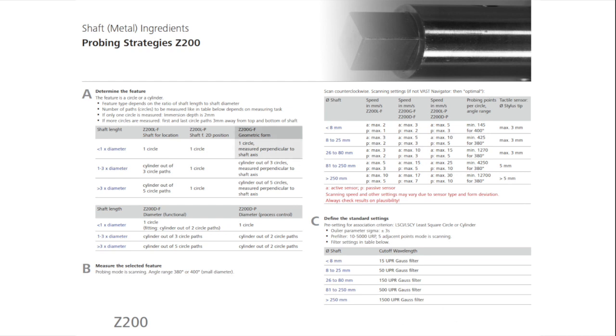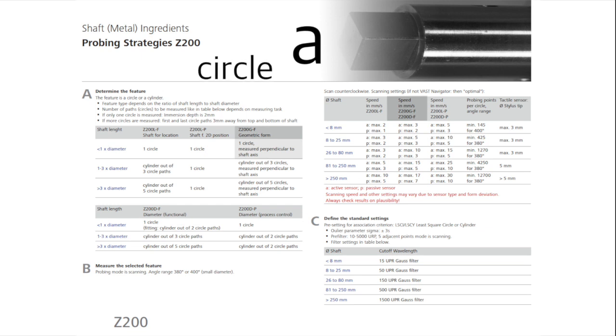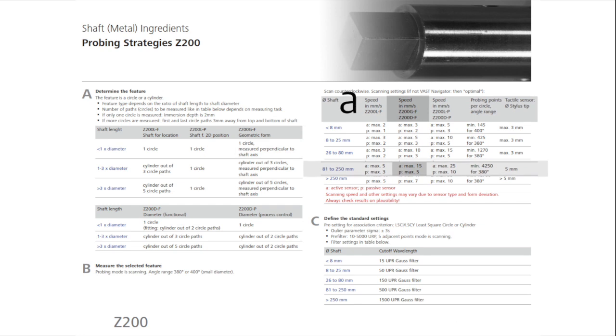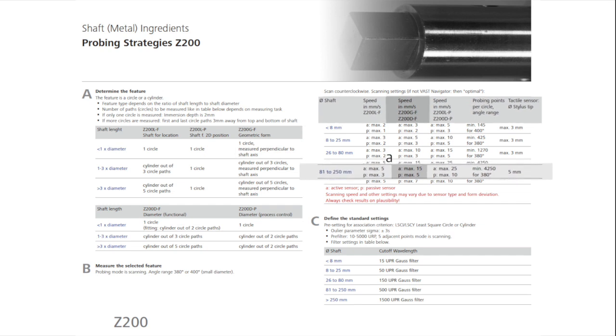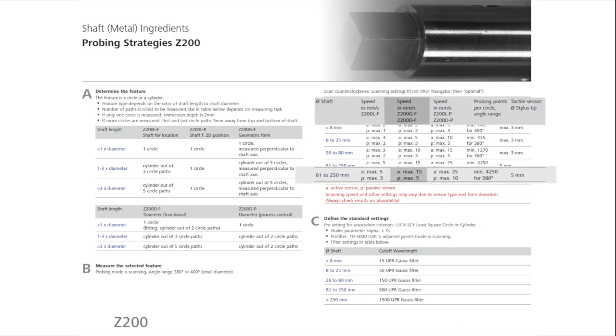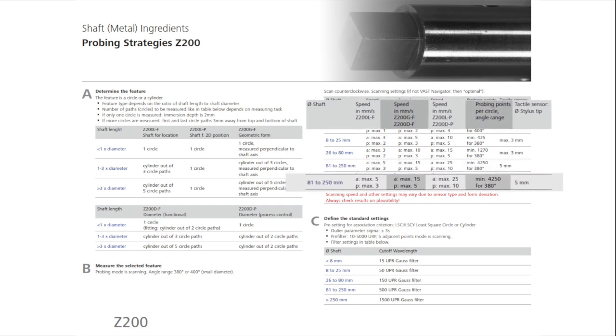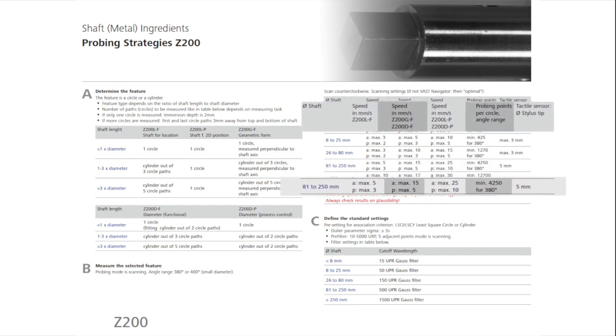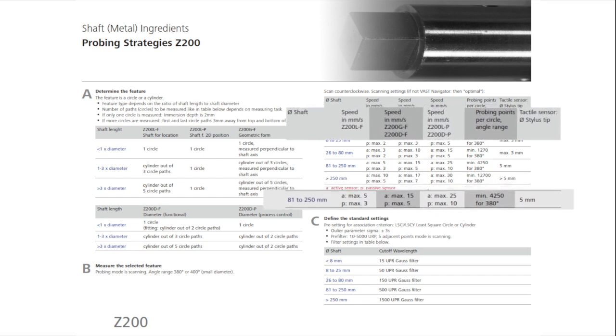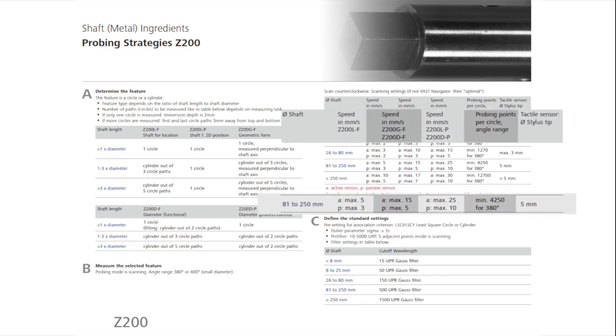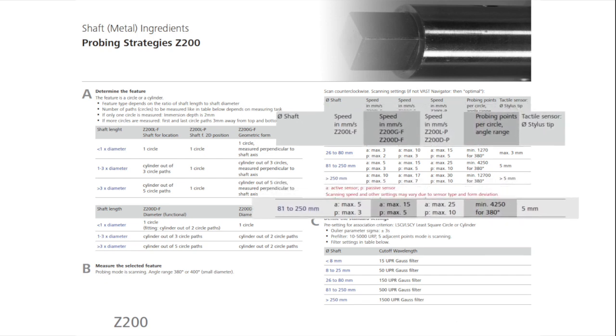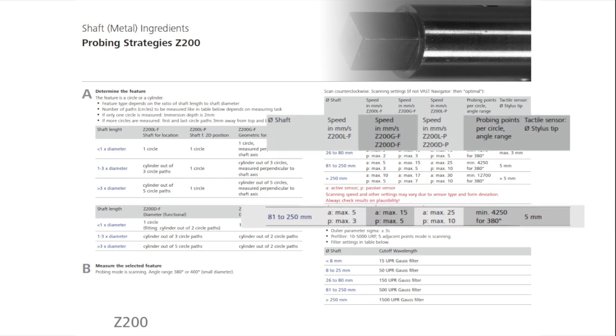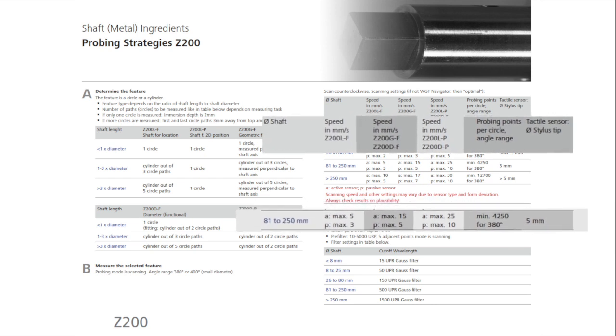When measuring with an active sensor, denoted by a lowercase a, the Cookbook recommends to measure a circle element in scanning mode at a maximum speed of 15 mm per second. The circle element should be measured with a minimum of 4,250 points, a 380-degree scan path, and a stylus with a diameter of 5 mm.